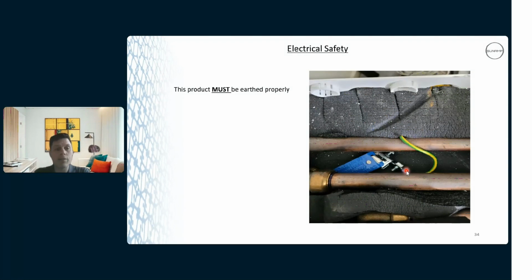The product must be earthed properly. The amount of times I see this when I go to a job, I've lost count. We've got an earth clamp here, which we ask to be fitted ideally onto the cold mains pipe, but all the pipes are connected to the heat exchanger. Sometimes the cold mains has a shorter length on it, depending on the exit or entry, so you might not have enough space for that earth clamp, so you can fit it on another pipe if you want to.